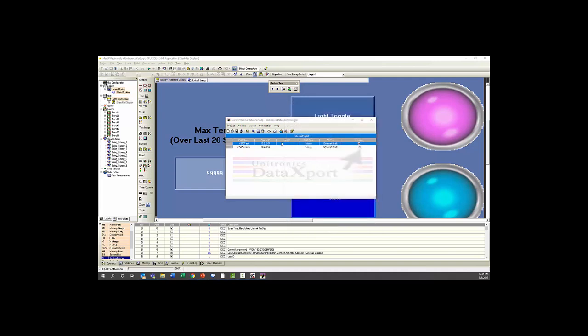You have schedules. You can have multiple schedules, so each PLC can be pulling from a different schedule and the different data table or region you want to connect to. You have your direct connection, and you can either use, and you use Ethernet call here, and you would put in the IP address, whatever the IP address of the unit you're connecting to would be, the protocol you're using. We recommend TCP so you don't have any lost or dropped data, and the port number you're connecting to. We use the default here of 20256. You'll also have the option to create a file using a template or just a CSV file. What you can do, you can press apply, and then okay, and now you'll see this new PLC or new site pop up here. So we're not going to enable this because this PLC doesn't actually exist.